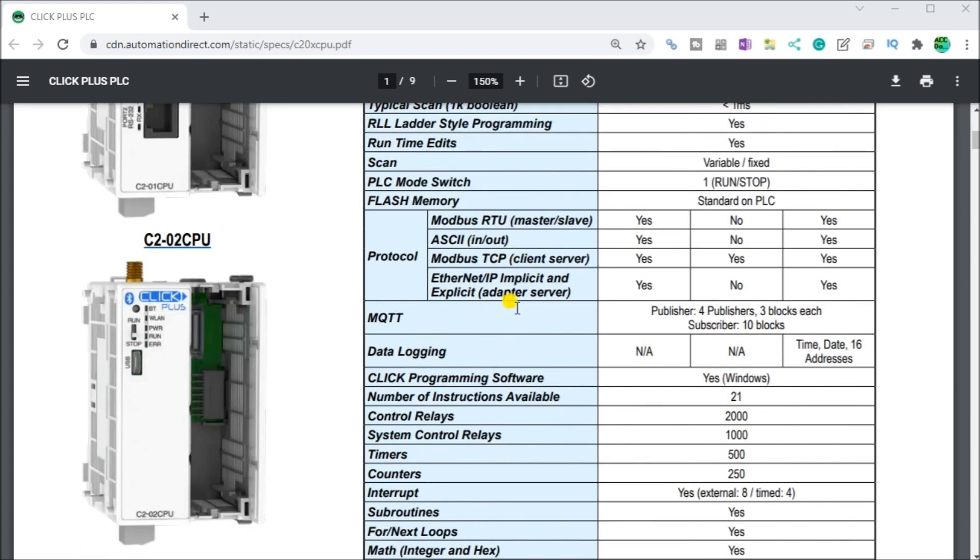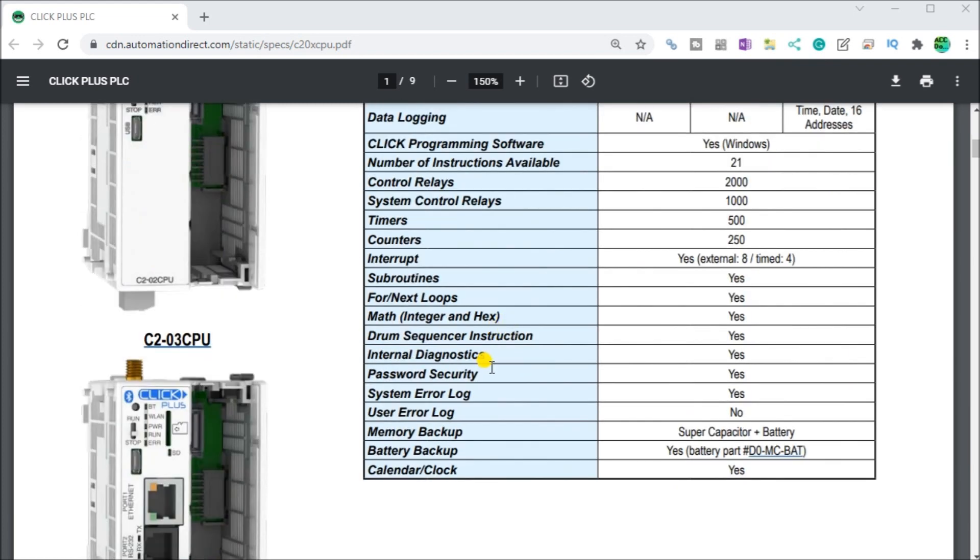Then we look down further, we have logging and at the bottom here you see the memory backup. We have a super capacitor plus battery. Looking at the specs, the super capacitor will hold this memory for one hour. After one hour we'll lose it, but since we have a battery or we install a battery into our controller, then we're able to keep that on for three years.